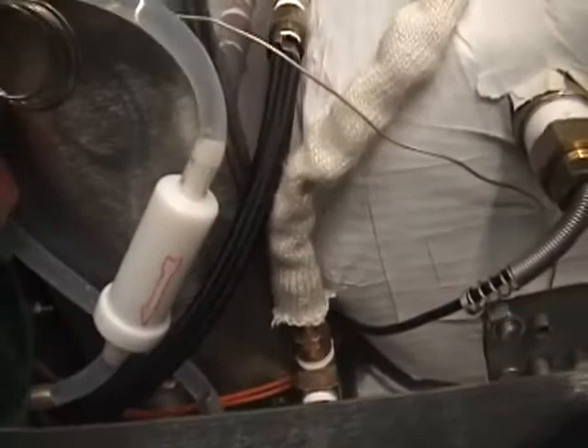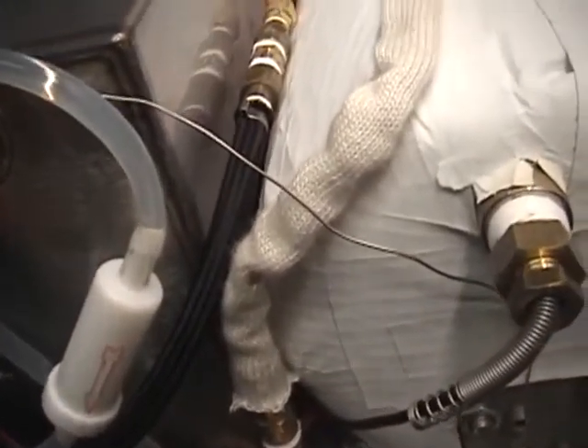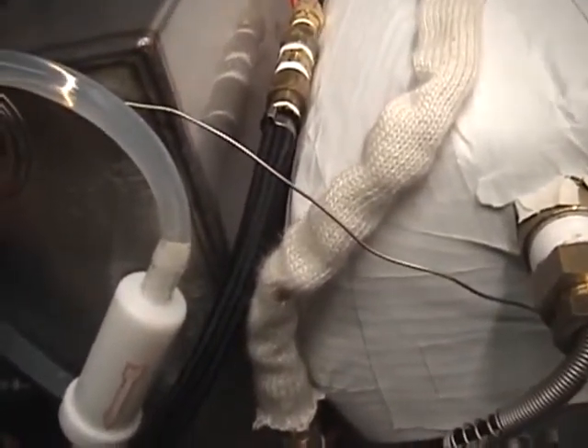On replacing the pump on model 400. First of all, make sure there's no pressure in the machine and that the machine is unplugged. Number two, you will need to remove two bottom bolts that are towards the front of the machine that hold the electrical plate.